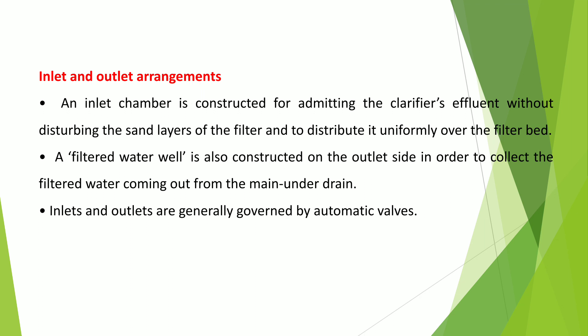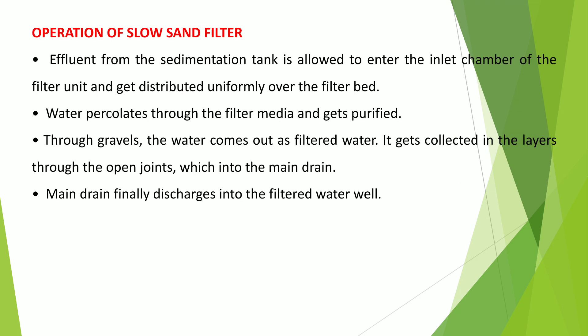An inlet chamber is constructed for admitting the clarified effluent without disturbing the sand layers and to distribute it uniformly over the sand filter. The filtered water well is constructed on the outlet side to collect the filtered water coming out from the main under-drain. Inlets and outlets are generally governed by automatic valve systems. Effluent from the sedimentation tank is allowed to enter the filter unit and distributed uniformly over the filter bed, then percolates through the filter media and gets purified.